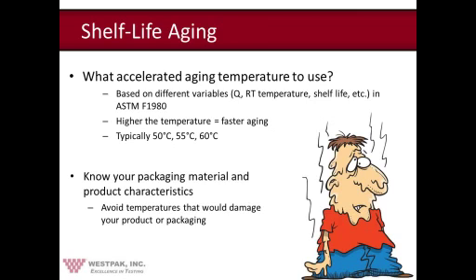In a few slides, Nora is actually going to go into a little more detail on manipulating these factors. But the bottom line is the higher the temperature you use, the faster the aging. However, the caution is that you don't want to go too hot because you may actually damage your product. So our recommendation is go ahead and speed up this test with a higher temperature, but you only want to go with a temperature that your packaging can safely withstand.